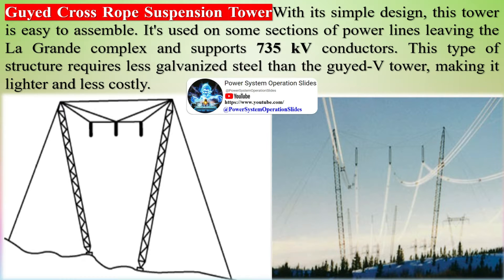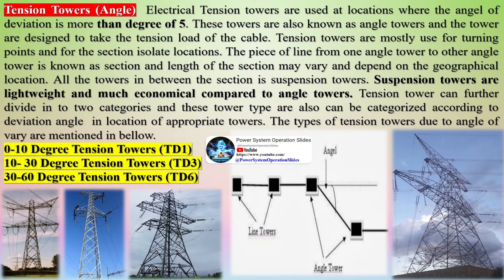Electrical tension towers are used at locations where the angle of deviation is more than 5 degrees. These towers are also known as angle towers and are designed to take the tension load of the cable. Tension towers are mostly used for turning points and for section isolate locations.